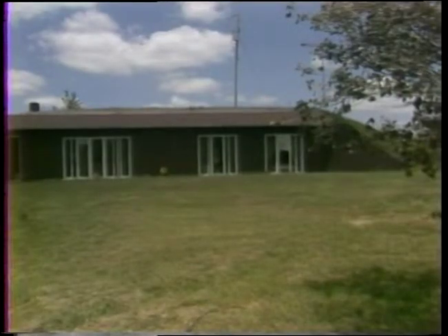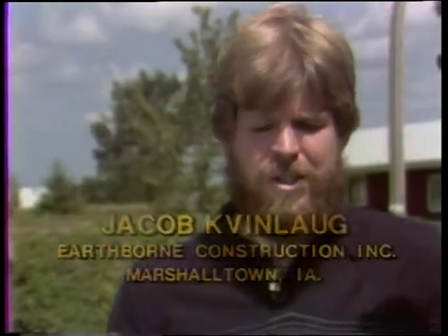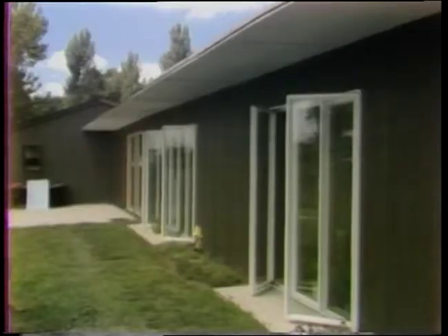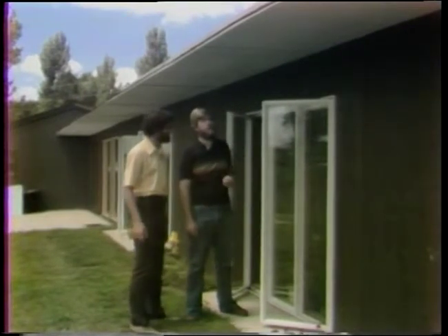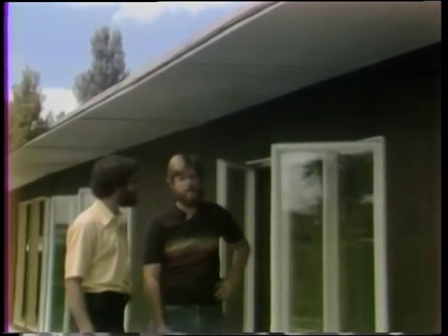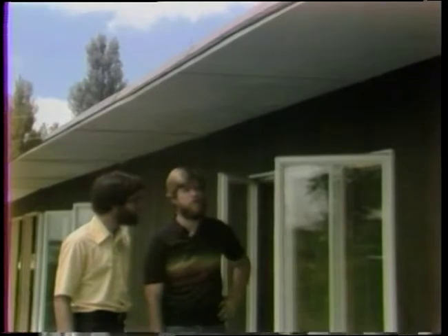What did the site look like before you started? It was a gently sloping south slope. We had to dig in about six feet, built the house, and then used the excavation earth to cover over the building. A sloped site isn't absolutely necessary, but it does help a little. We oriented the building to solar south — about six degrees east of compass south — to get maximum solar radiation. An important feature in passive design for summer cooling is the solar overhang. In this particular case, it's about 41 inches long, designed to keep the sun completely out of the windows from April 21st to August 21st.